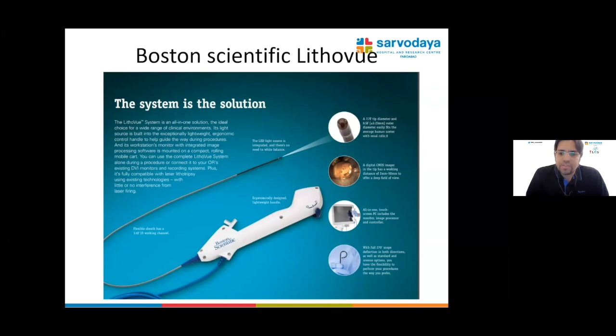So this next commonly used scope is Boston Scientific LithoVue. This is actually probably the most used and the most studied disposable flexible ureteroscope. It has the advantage of a slightly thinner tip diameter, that is 7.7 French, but the shaft is as thick as Pusen, that is 9.5 French. It has a digital CMOS tip, and it comes with a touch screen which is very user friendly, and you can deflect it on either side 270 degrees.